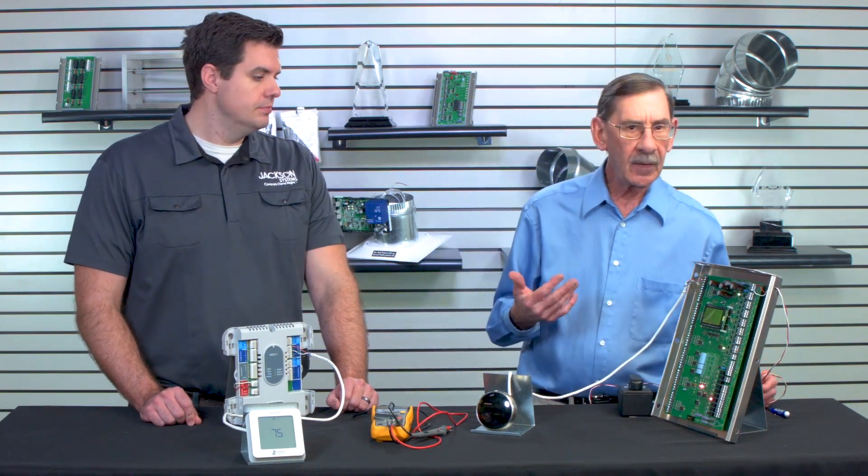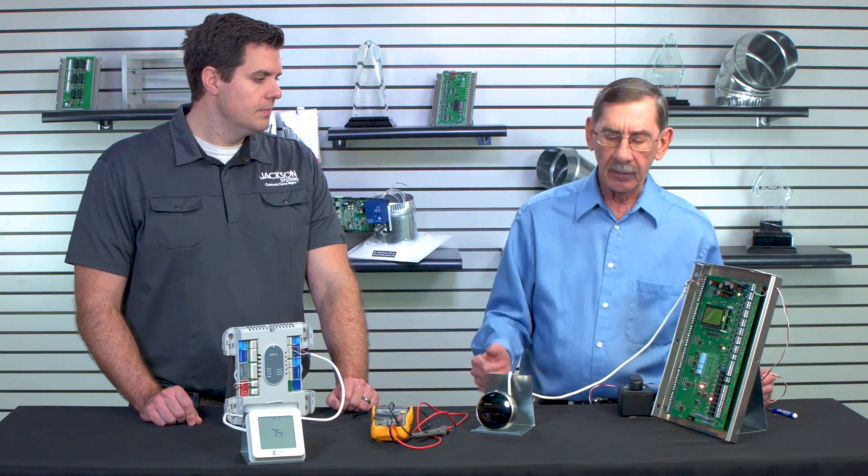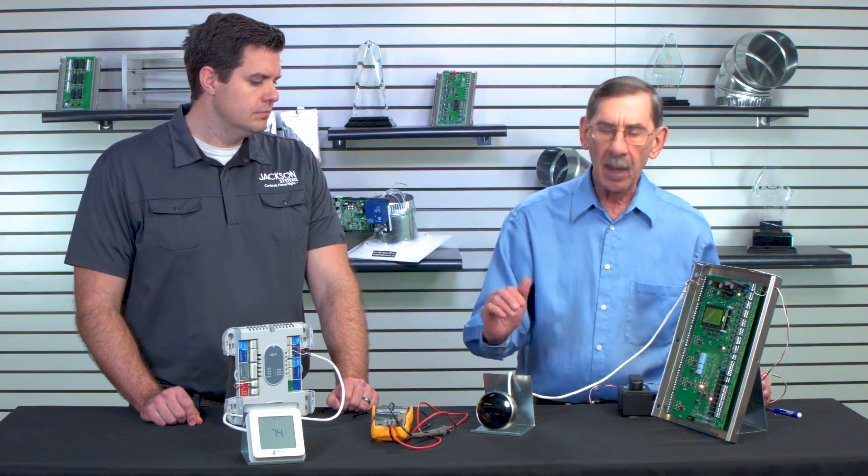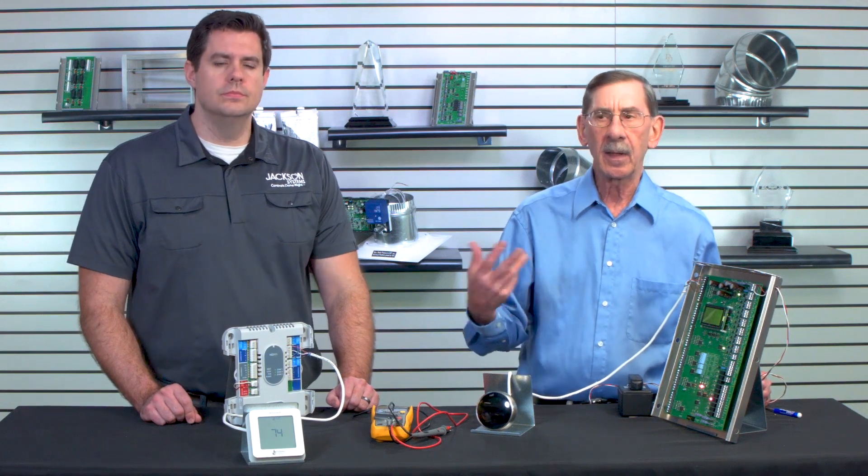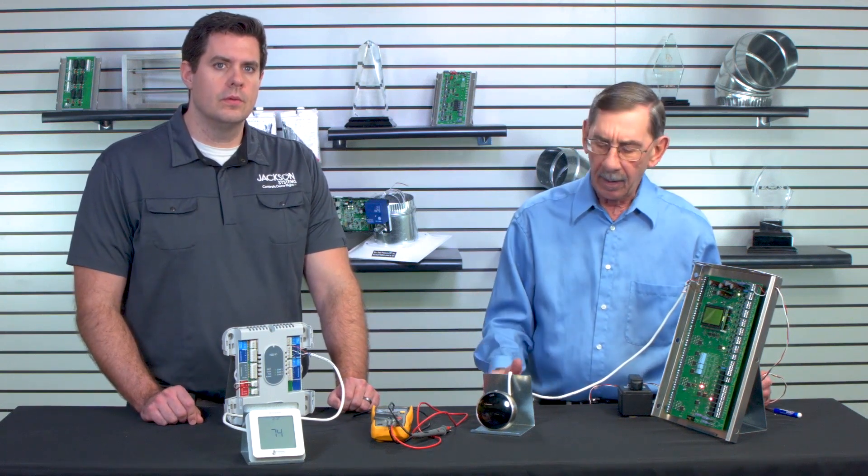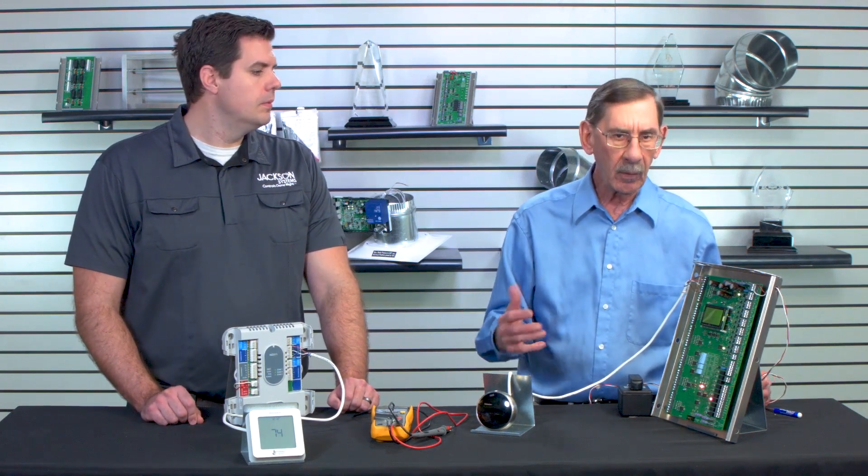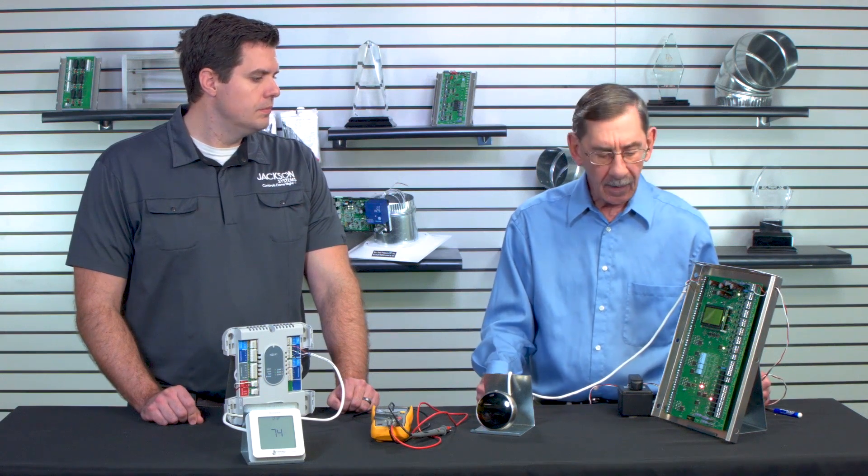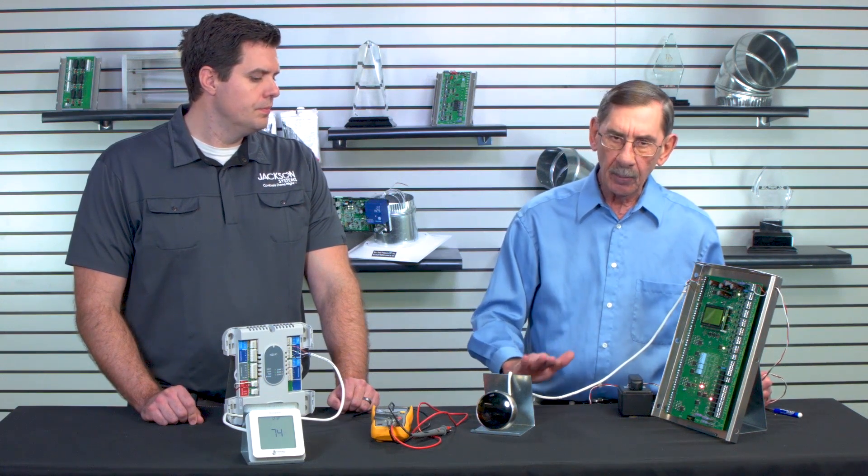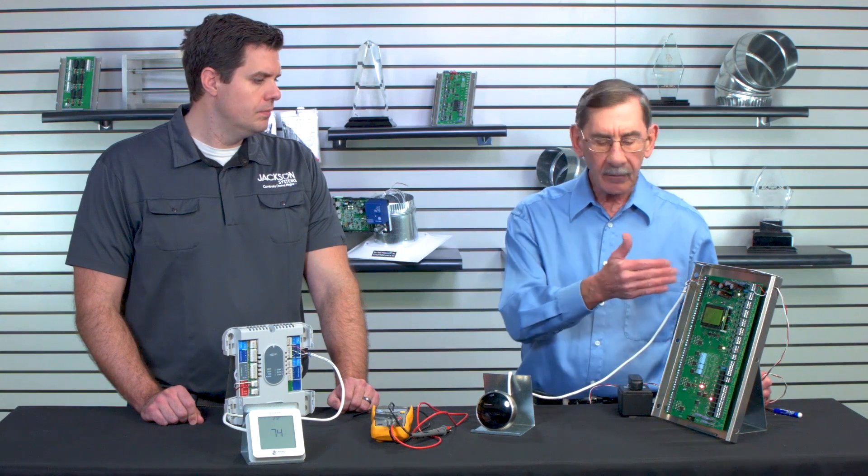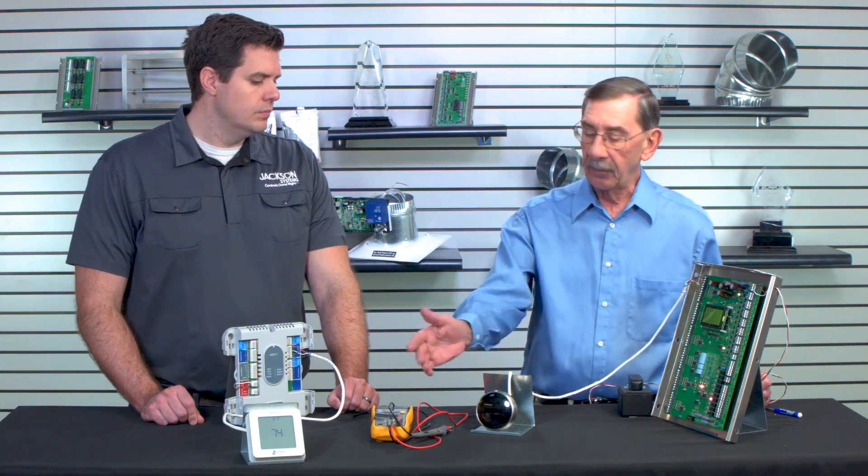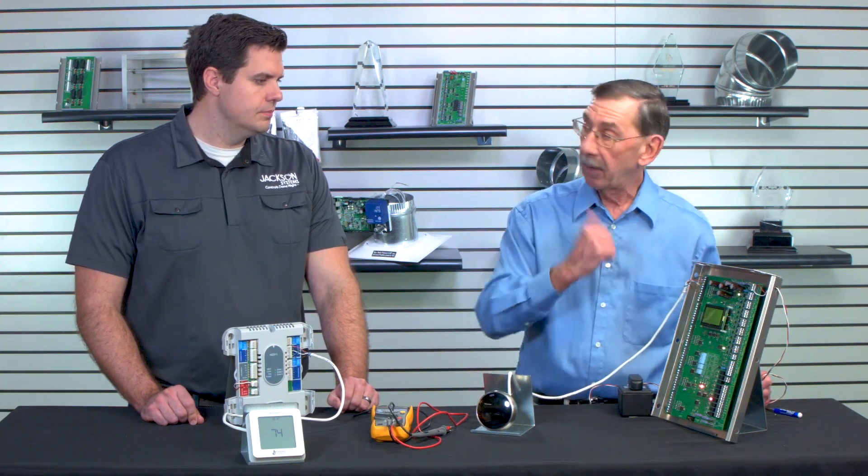So it's very easy to diagnose inputs and outputs on these panels. It doesn't matter whose thermostat it is. Like I said, if it's battery powered, that's fine. If it's hardwired with 24 volt power to it, that's fine. But very simple through the process of elimination to determine where the problem is here, wire, or there.